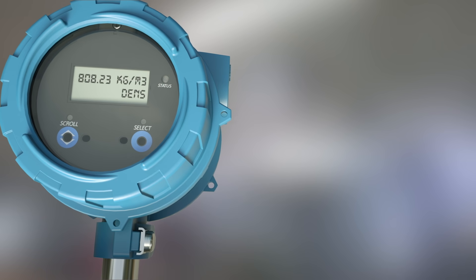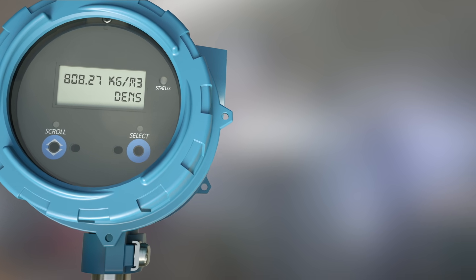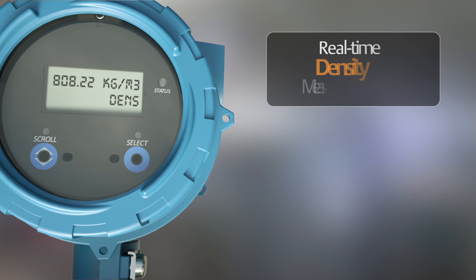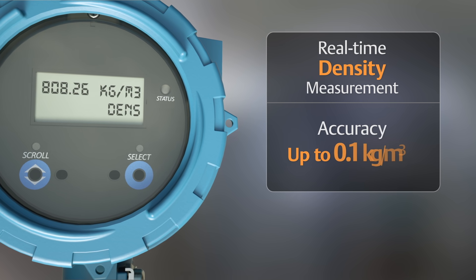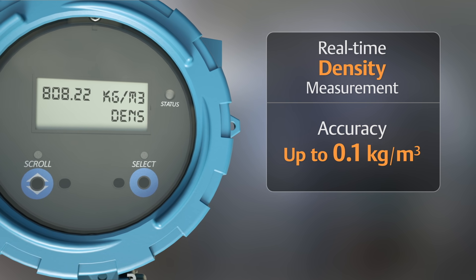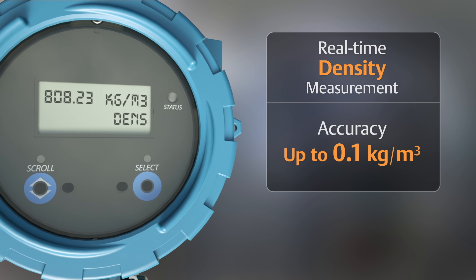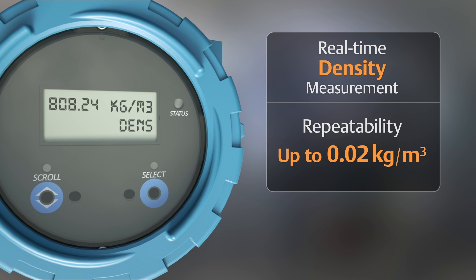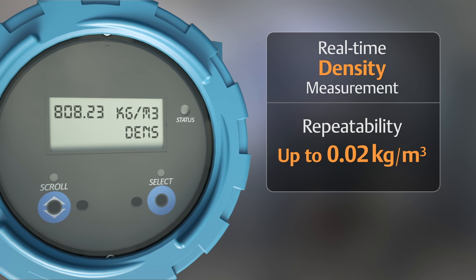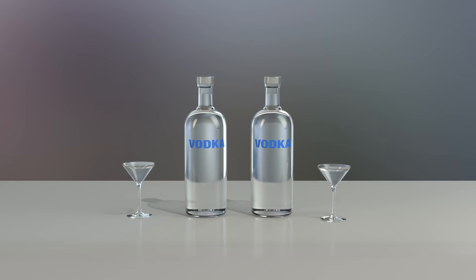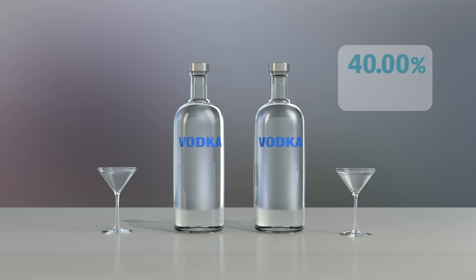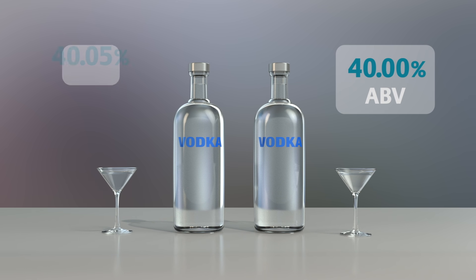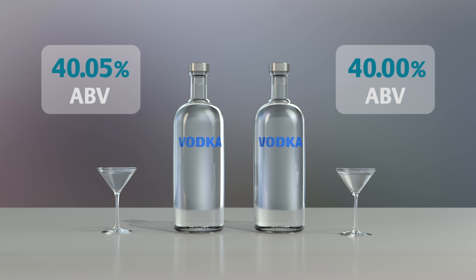Let's look at some of the key features of the Compact Density Meter. The meter provides real-time inline density measurement with up to 0.1 kg per cubic meter density accuracy and up to 0.02 kg per cubic meter density repeatability. For example, this means the meter is sensitive enough to detect the difference between a concentration of 40.00% and 40.05% alcohol by volume.